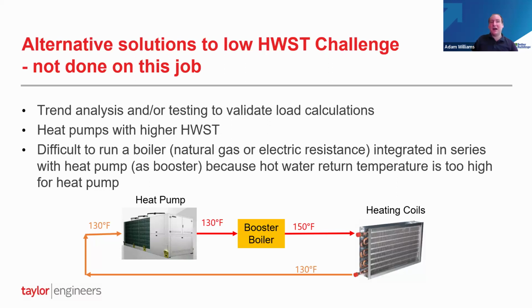I should clarify what Kyle said about adding a gas boiler or an electric boiler to supplement. That's a fine approach, and it's very practical in many cases. But you just need to be aware that it's sometimes hard to run your heat pump and a booster machine at the same time, and that if you plan on a booster boiler on the peak, coldest days of the year, it may make more sense to size that to run without the heat pump doing anything, because it may not be able to do anything if you need those high hot water temperatures to work. Why don't we go to the next slide?